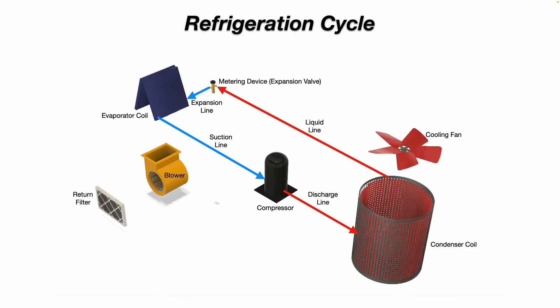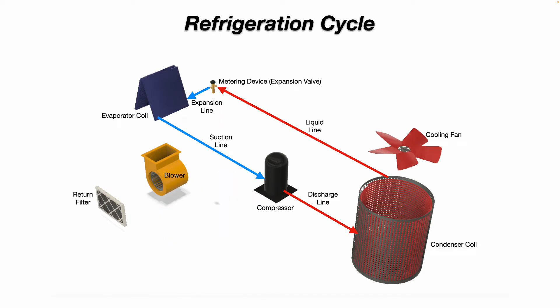You really need to know and memorize the refrigeration cycle and the main components in a refrigeration system. The compressor is the heart of an HVAC system. A compressor should only pump vapor refrigerant — you should never have liquid refrigerant going into a compressor, as it can slug and damage the compressor. The compressor is the refrigerant pressure increaser.